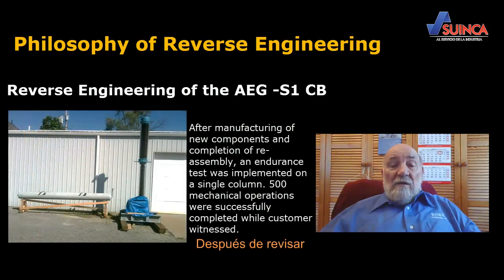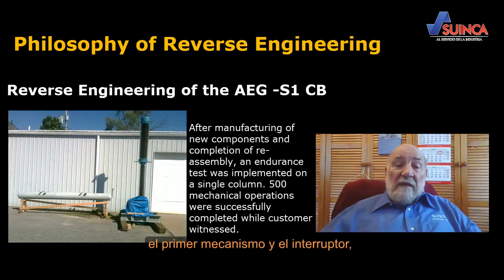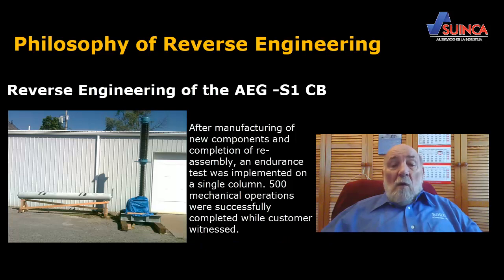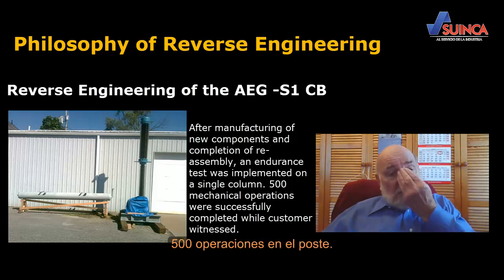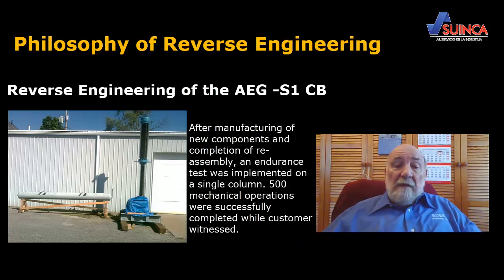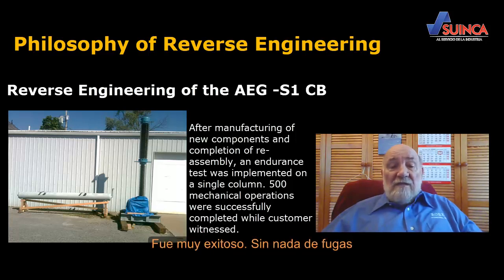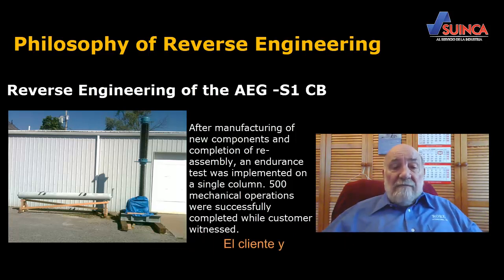After we did the overhaul of the first mechanism and the breaker, we completed about 500 operations on the pole. It was very successful, no leaks, no nothing. The customer and Suinca came to Warrendale to witness the test.